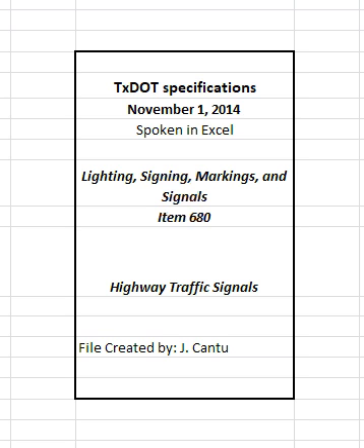3.1.1.3 Wiring. Furnish stranded number 12 AWG/XHHW conductors. Install above-ground cables and conductors in rigid metal conduit, except for span wire suspended cables and conductors, drip loops, and electrical wiring inside signal poles unless otherwise shown on the plans. Make power entrances to ground-mounted controllers through underground conduit. Wire each signal installation to operate as shown on the plans.